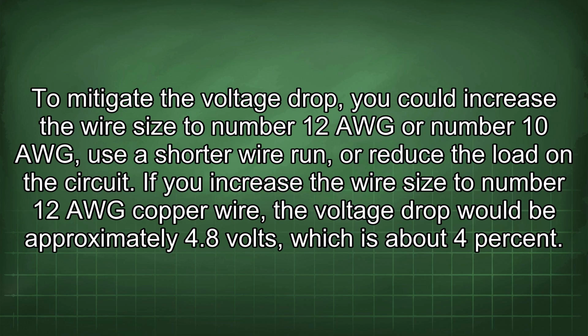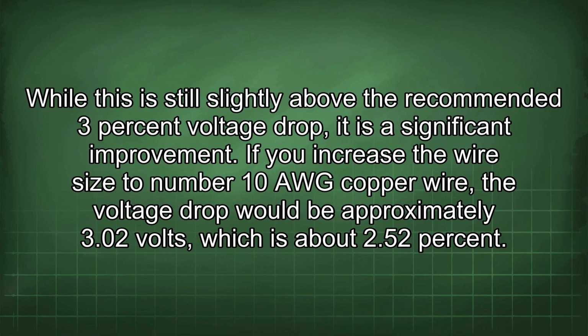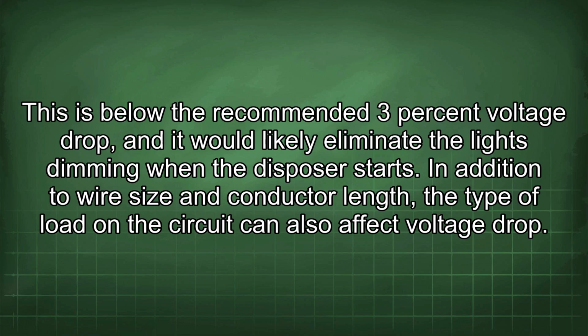If you increase the wire size to number 12 AWG copper wire, the voltage drop would be approximately 4.8 volts, which is about 4%. While this is still slightly above the recommended 3% voltage drop, it is a significant improvement. If you increase the wire size to number 10 AWG copper wire, the voltage drop would be approximately 3.02 volts, which is about 2.52%.